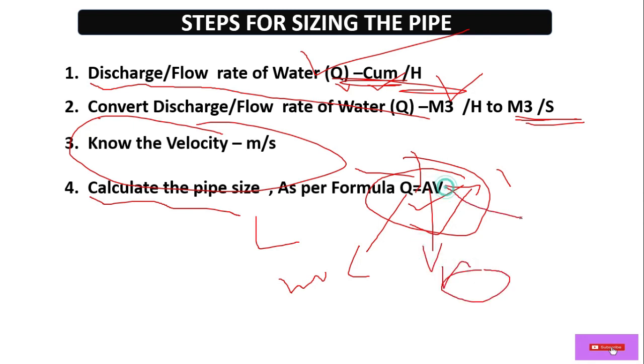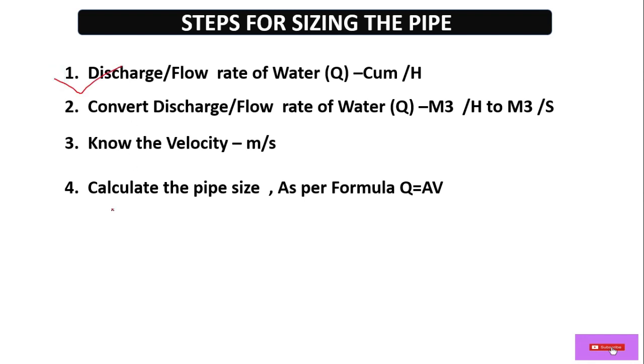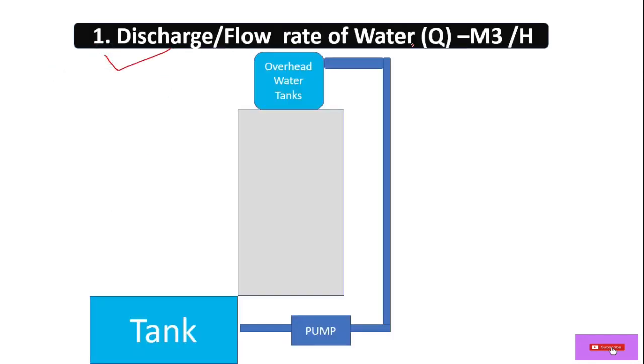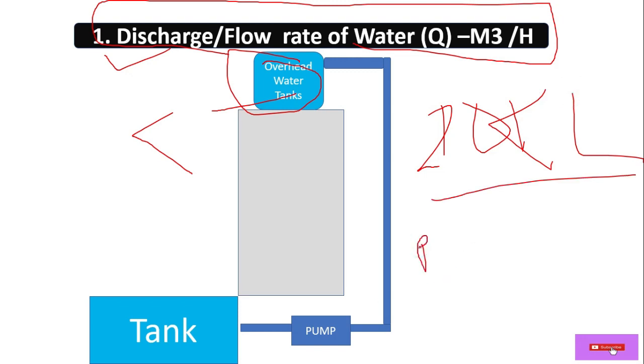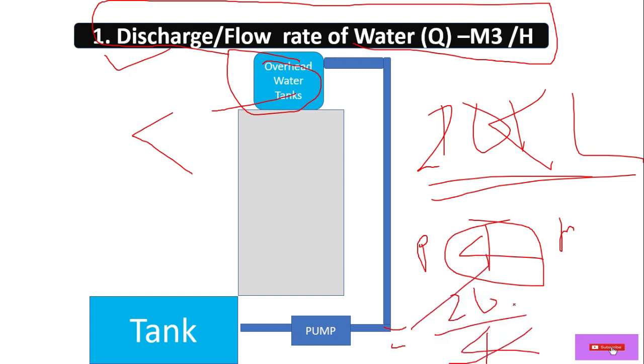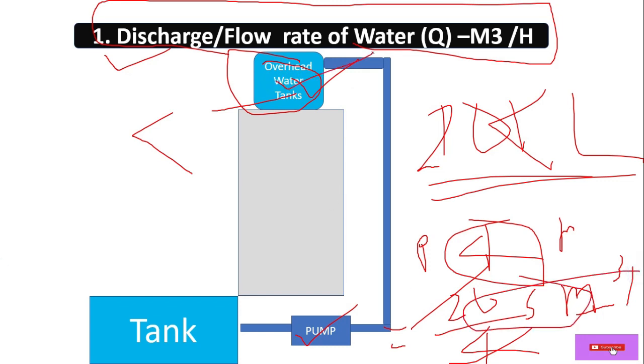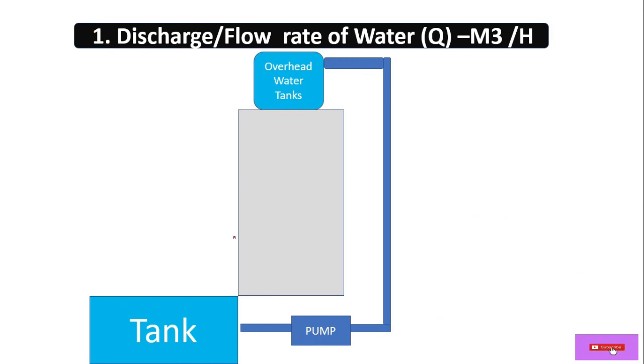In Step 1, we need to know the value of Q — the discharge or flow rate. Basically, flow rate means: if our tank capacity is 20 KL and our peak hour is 4 hours, then 20 divided by 4 equals 5 cubic meters per hour. So if we select a pump with a discharge of 5 cubic meters per hour, the tank will fill up in 4 hours.